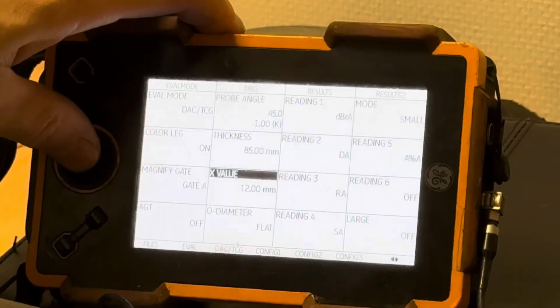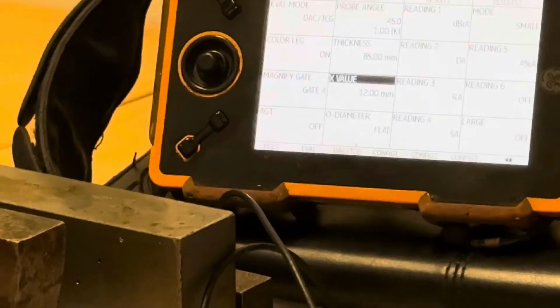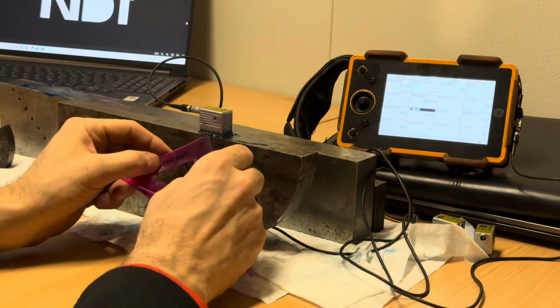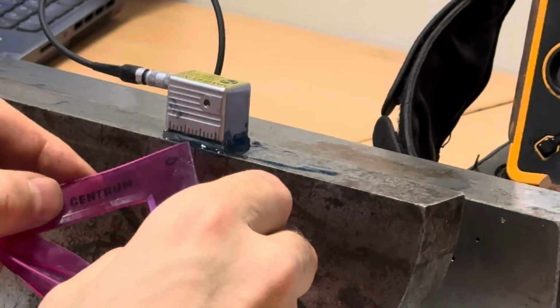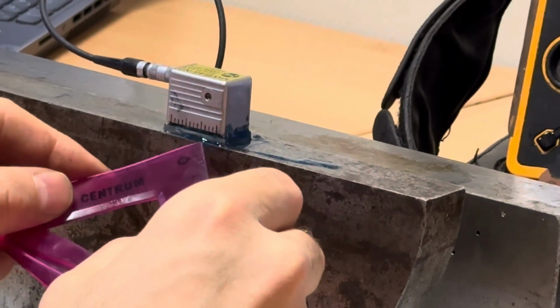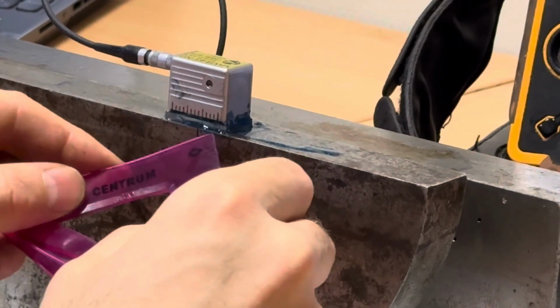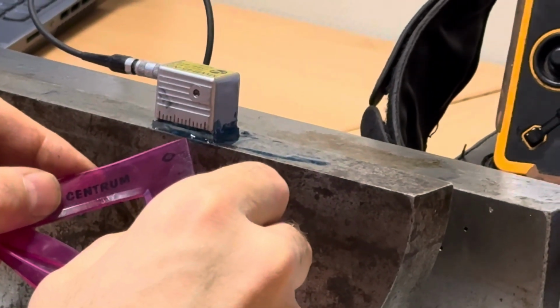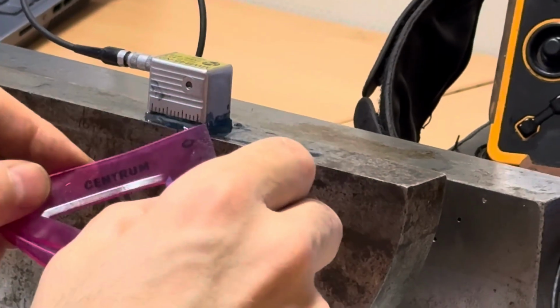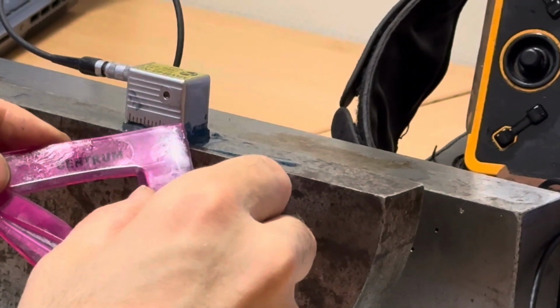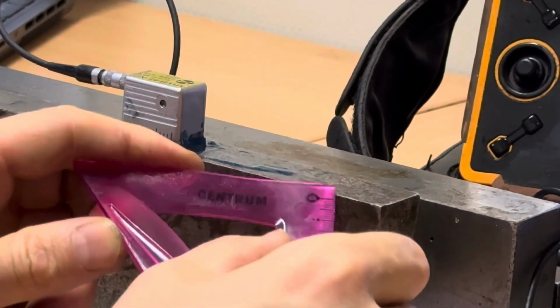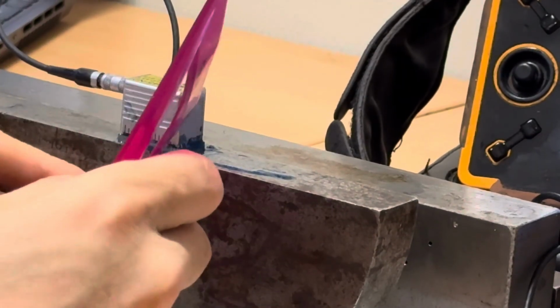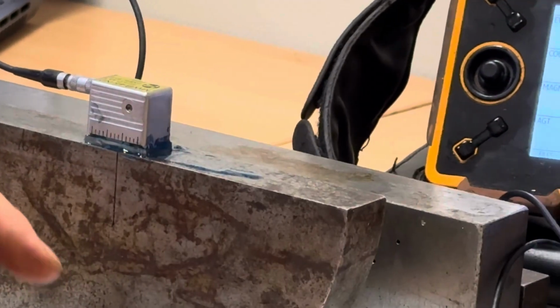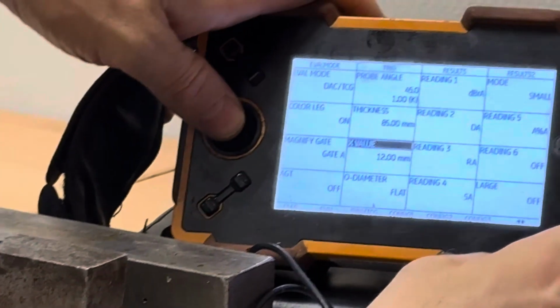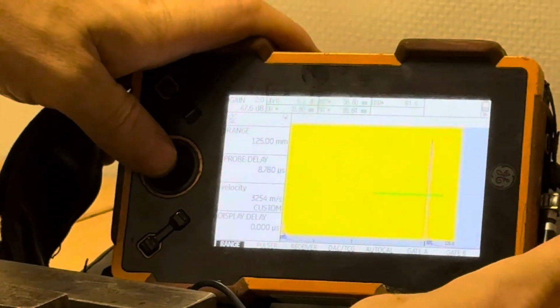What is the x-axis offset? It's the distance from where the probe beam initially fires to the very start. We take that into account. Here it is, displayed, so that the device calculates from the defect's true start to the defect itself, not from the center, but from its beginning. So we've set it to 12, and with that completed, we exit.